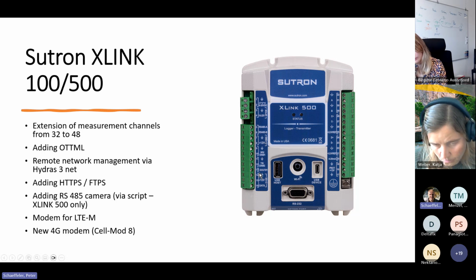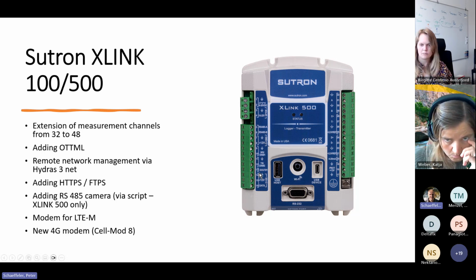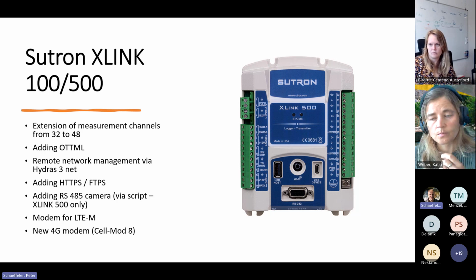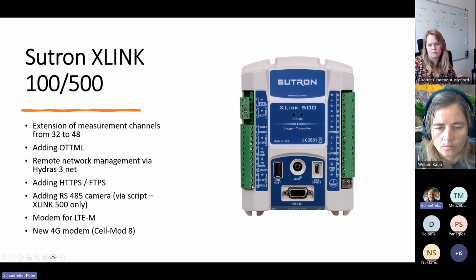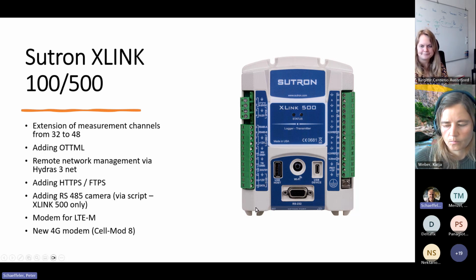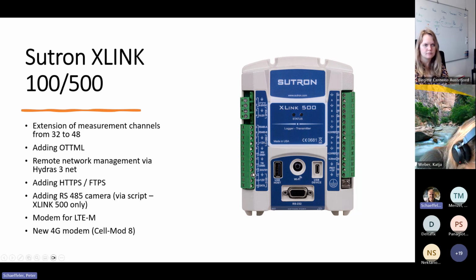The main application would be a flood warning situation, where your level rises above a defined threshold. When this happens, the X-Link initiates the camera to take a picture and send it to a server, something like this. Pictures can also be stored on an SD card in the X-Link and read out later, or copied down, or transmitted via the internal modem.